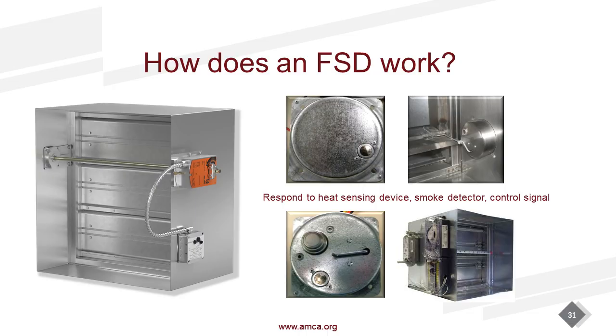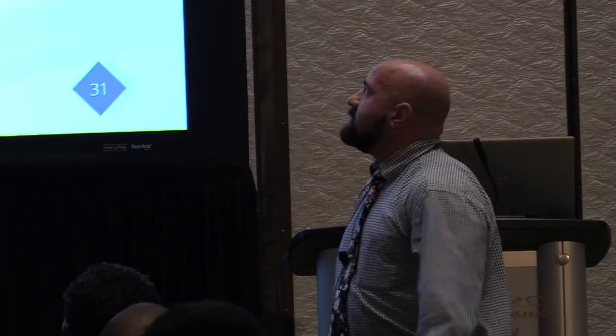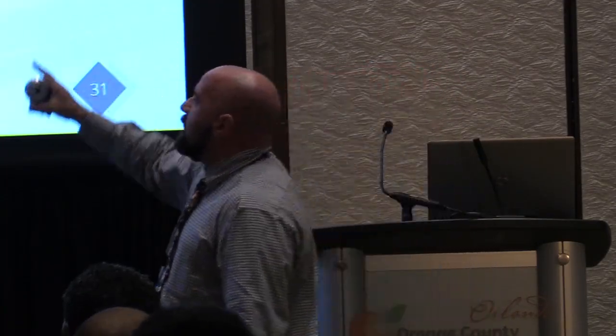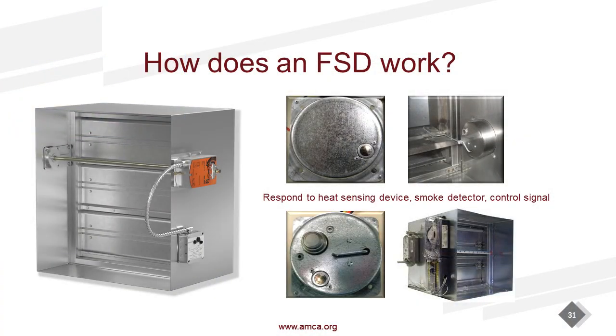So we talked about the fusible link closure of a fire damper. Well, fire smoke dampers respond to a heat sensing device, a smoke detector, or maybe a control signal. In the center there, that's what we call a resettable, reusable link, right? So all of your specifications for fire smoke dampers have this resettable link, right? All it is is an electronic link. It's got a heat sensing device, that little circle. It's a thermal disc. As the air passes across it, it will literally pop, and it is wired in series with the actuator. It will break that series, the actuator will lose power, and the damper will close.